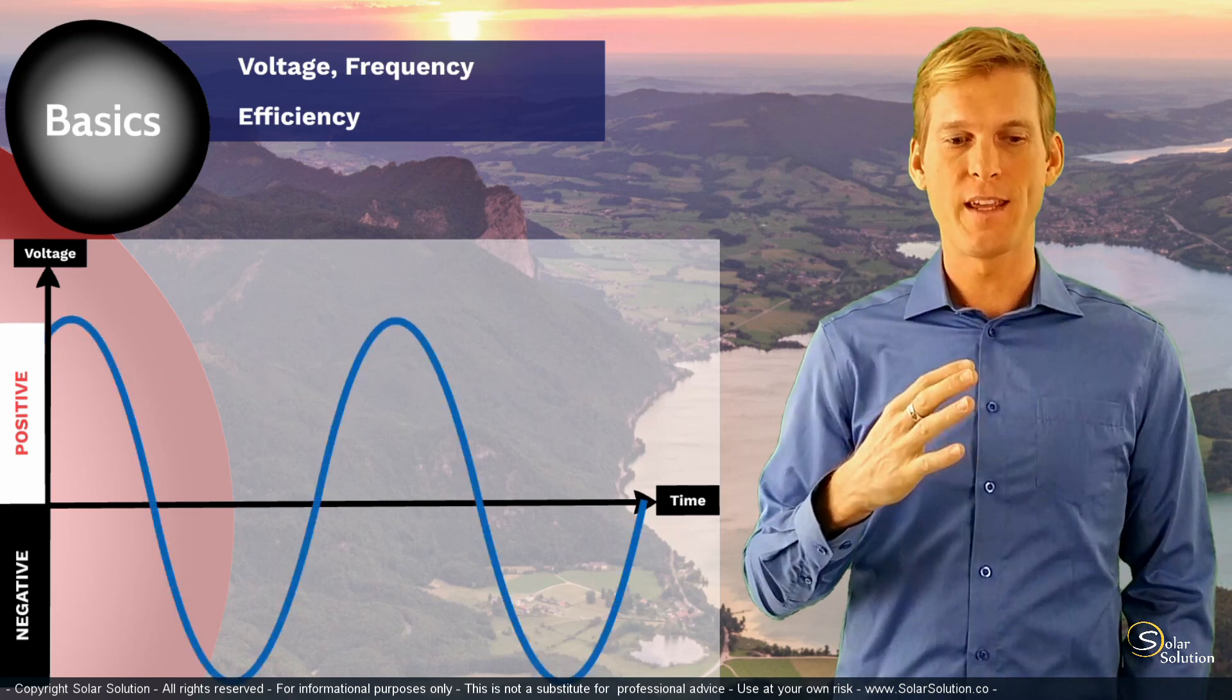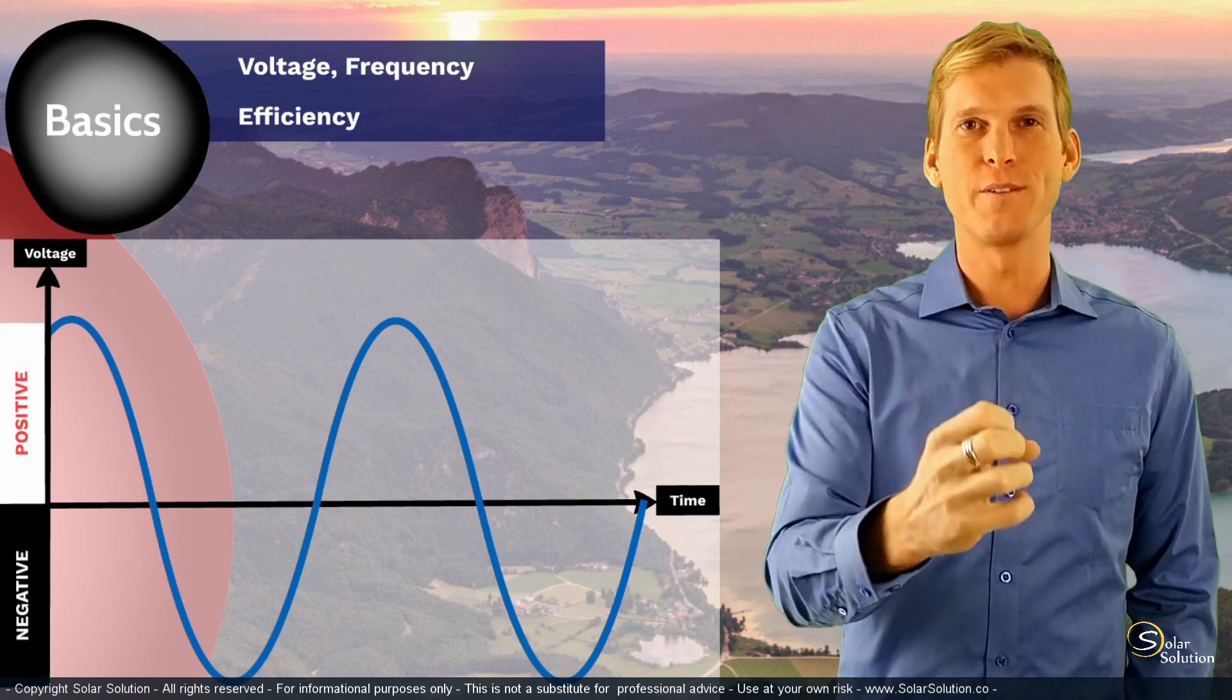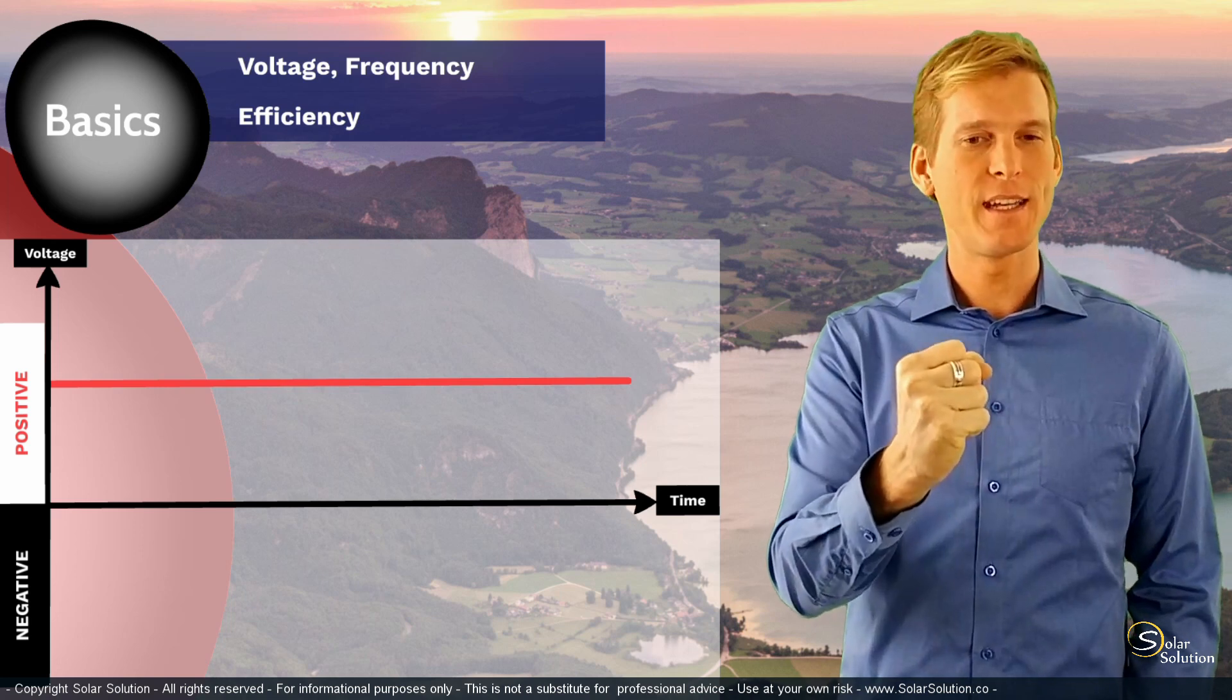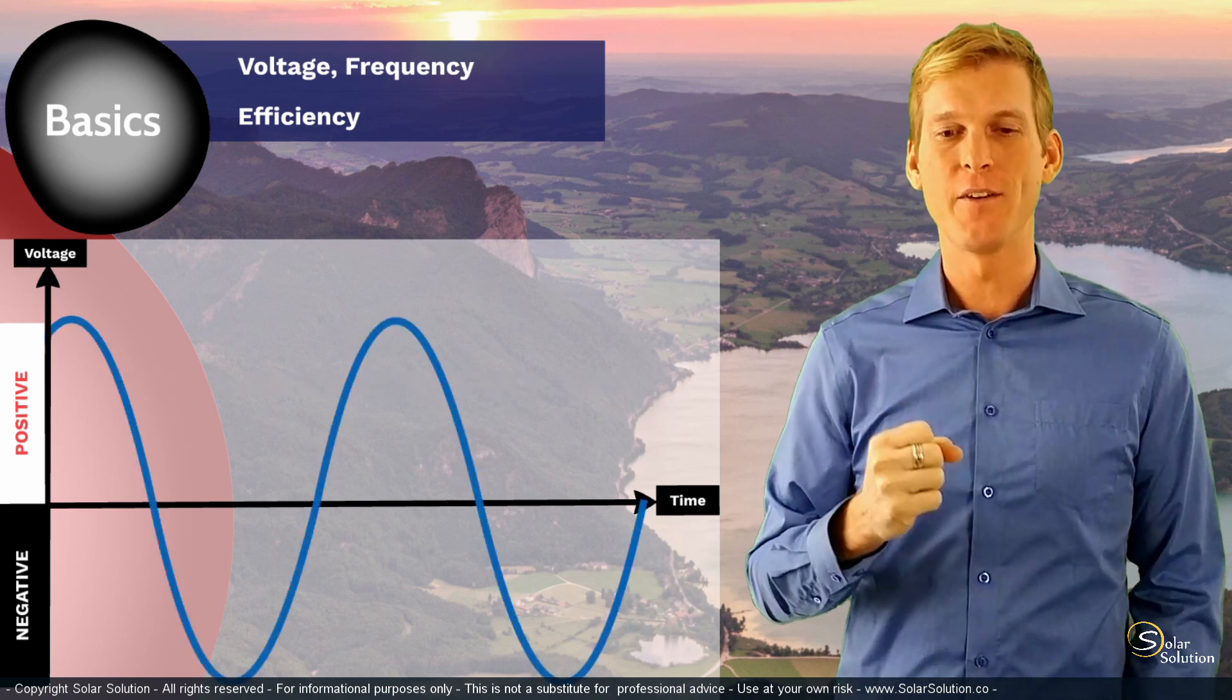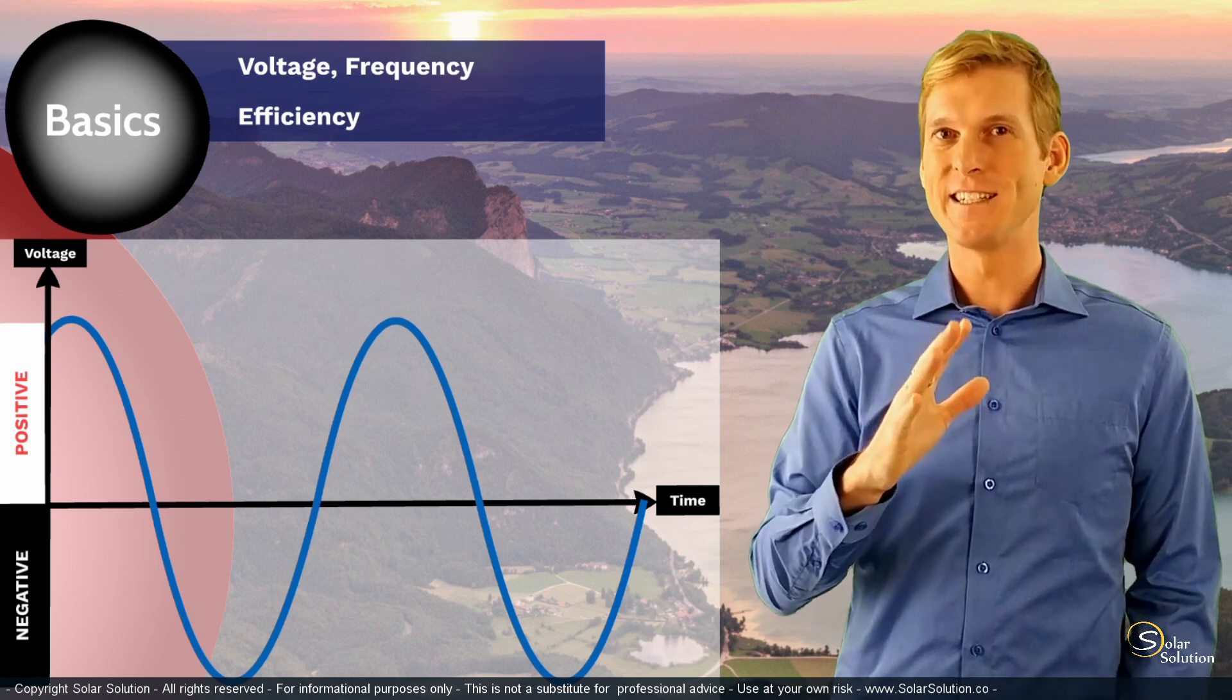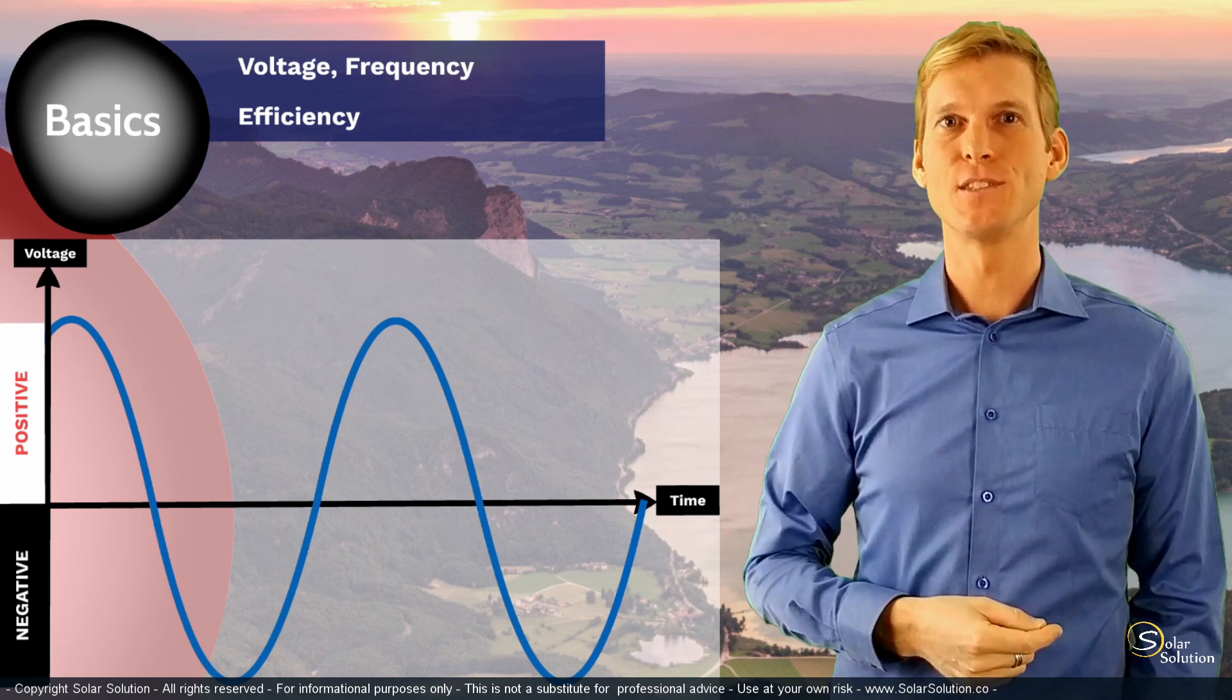A theoretical 100% efficient inverter would take all of the power from the DC source and convert all of that without any heat loss, any energy loss into an AC output. This 100% theoretical efficient inverter doesn't exist, but normally they range somewhere between 80 and 99% efficiency.